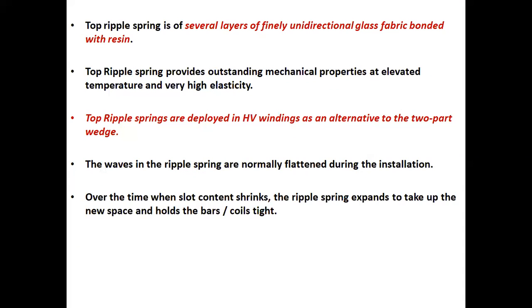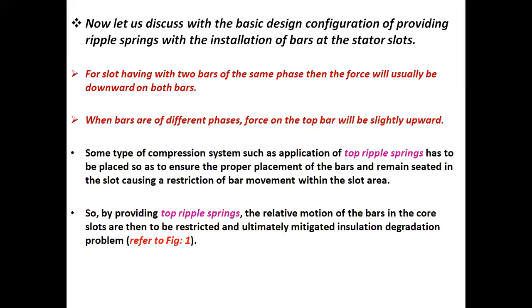The waves in the ripple spring are normally flattened during the installation. Over time, when slot content shrinks, the ripple spring expands to take up the new space and holds the bar or coil tight. Now let us discuss the basic design configuration of providing ripple springs with the installation of bars at the stator slots.